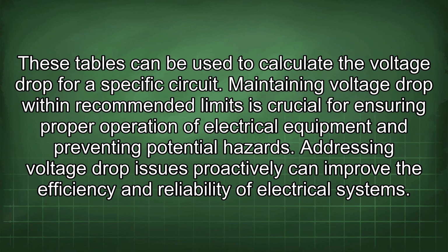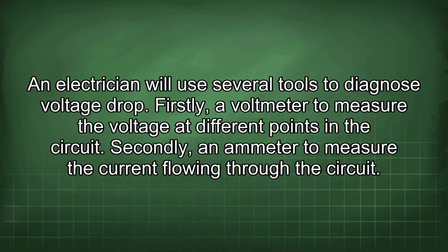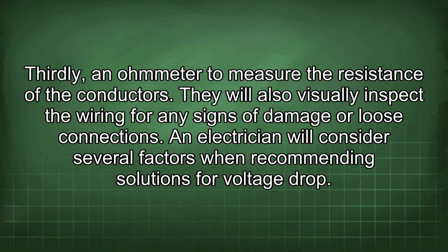Maintaining voltage drop within recommended limits is crucial for ensuring proper operation of electrical equipment and preventing potential hazards. Addressing voltage drop issues proactively can improve the efficiency and reliability of electrical systems. An electrician will use several tools to diagnose voltage drop. Firstly, a voltmeter to measure the voltage at different points in the circuit. Secondly, an ammeter to measure the current flowing through the circuit. Thirdly, an ohmmeter to measure the resistance of the conductors. They will also visually inspect the wiring for any signs of damage or loose connections.